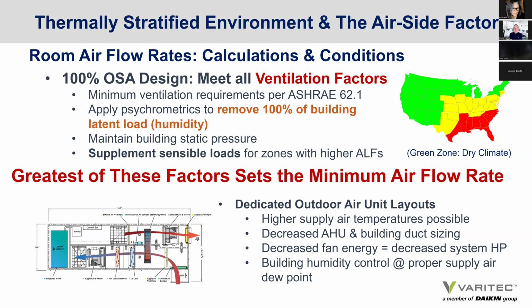Otherwise, you'll have condensation. The challenge that we've had, in my experience, with chilled beam systems and decoupled hydronic 100% outside air systems, has been inadequately designed outside air supply at dew points of 53 and 54 degrees, which is achieved at 55 degrees off a cooling coil. If you're using these systems, depending on your latent load in the space, you may want to look at 52 degrees, 50 degrees. Make sure your outside air is at a low enough dew point to absorb the moisture gains within that space to control relative humidity factors. So keep these design issues in mind.